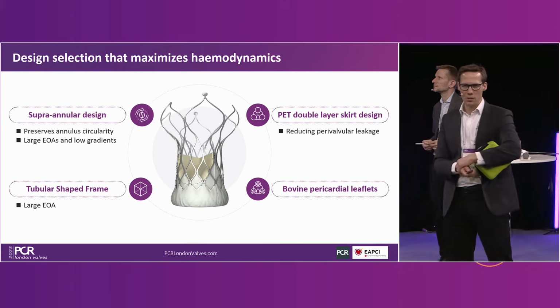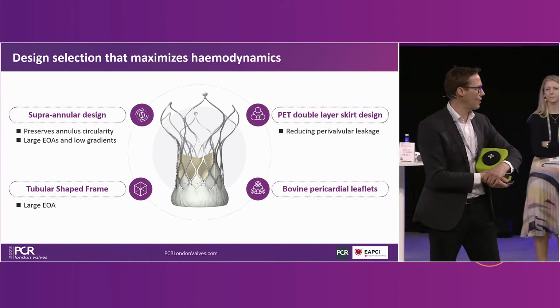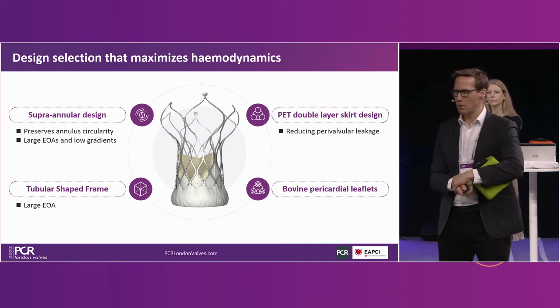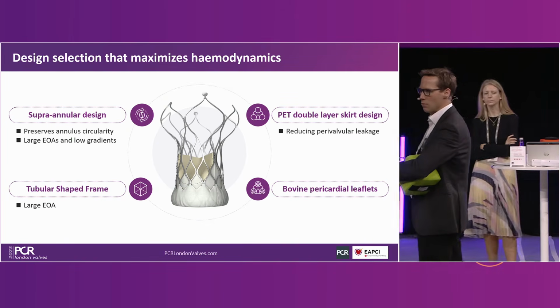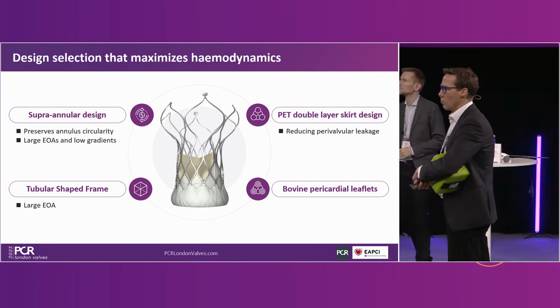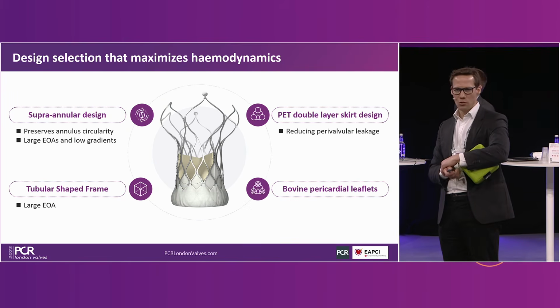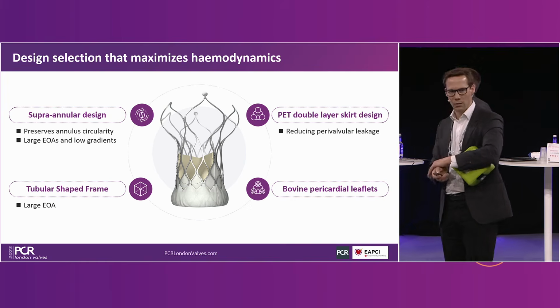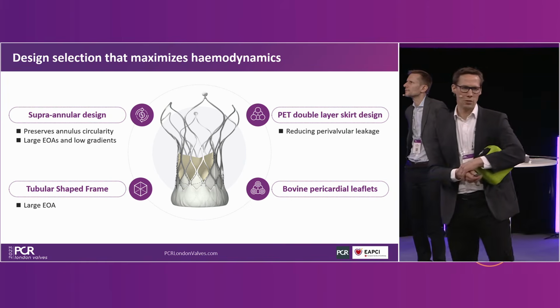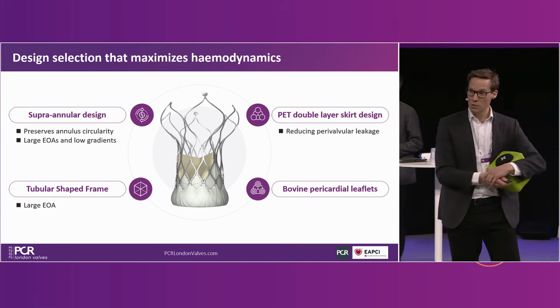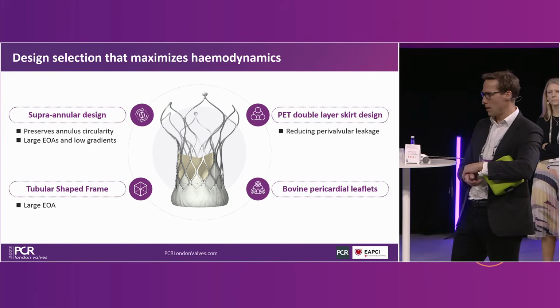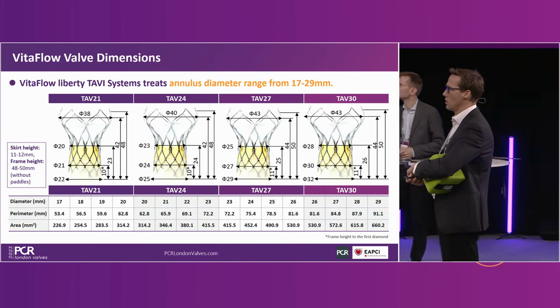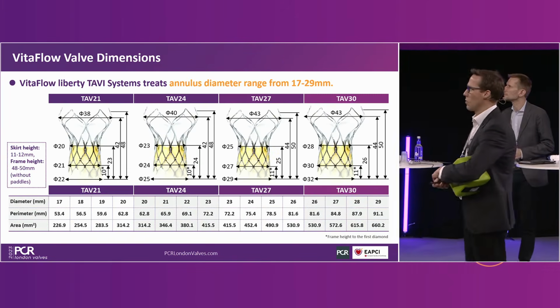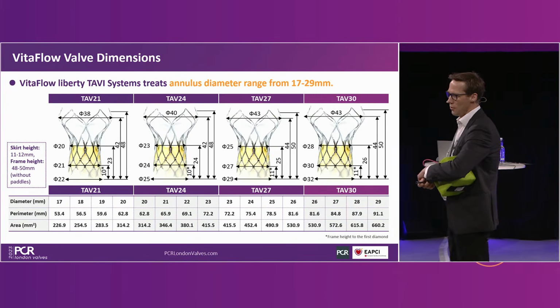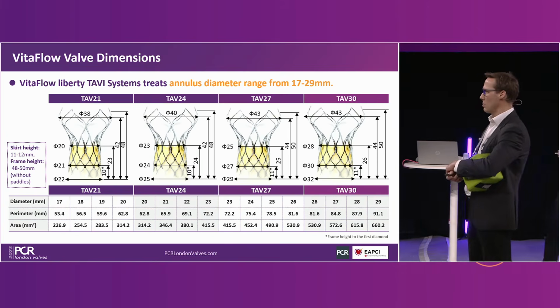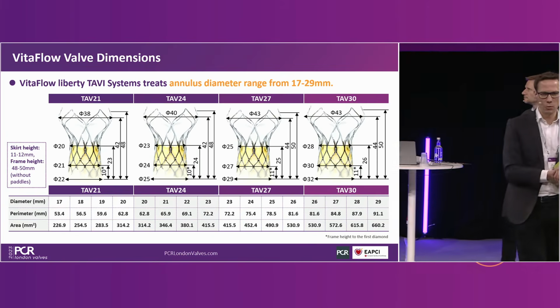The valve is a supra-annular design, of course. We have bovine pericardial leaflets, and that PET double layer skirt is really impressive in terms of reducing the risk of paravalvular leak. One thing to notice is that the frame is tubular shaped. It does not come in at the waist like other self-expanding valves. There are certain advantages to that in terms of effective orifice areas. There are also some disadvantages: you need to be very careful about the risk of coronary occlusion when using this device. The device comes in 4 sizes, 21, 24, 27, and 30, and it covers an annulus range, I work in perimeters, from 53 to 91. So really a good range of sizes.